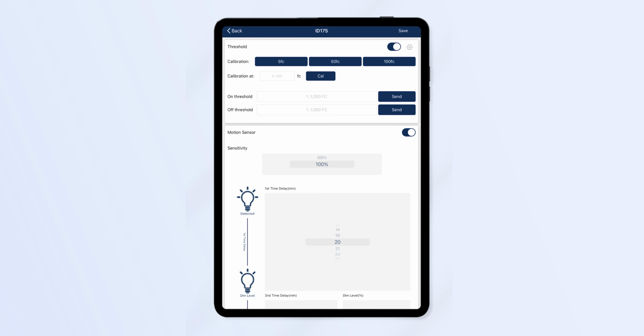For photocell sensors, either indoor or outdoor, the default on-off threshold is 10 to 60 FC or foot candle. Users can change the thresholds if they desire. Press the 5, 50, or 100 FC button to set the on threshold, and the lights will turn on and off several times to auto-calibrate the off threshold. Users may input a specific foot candle value as the on threshold and select the cal button to calculate the off threshold based on that.